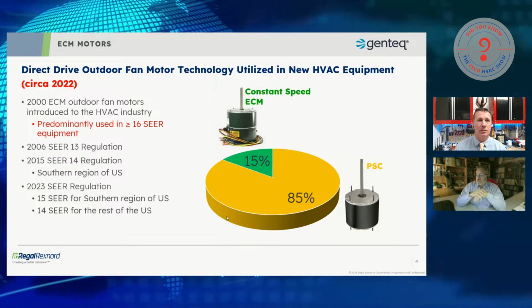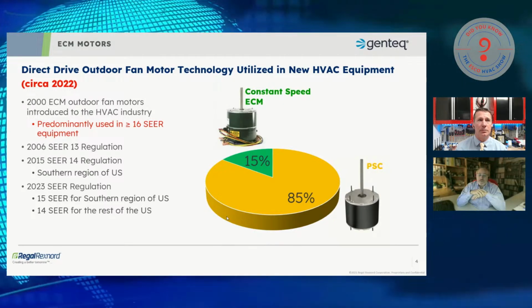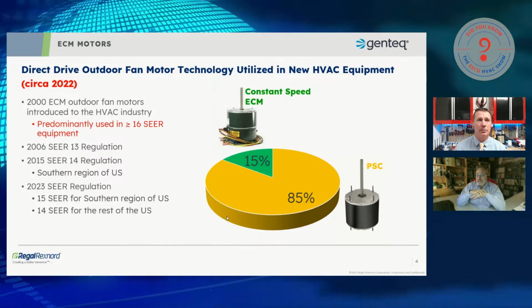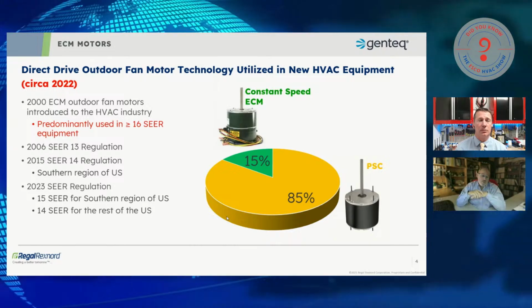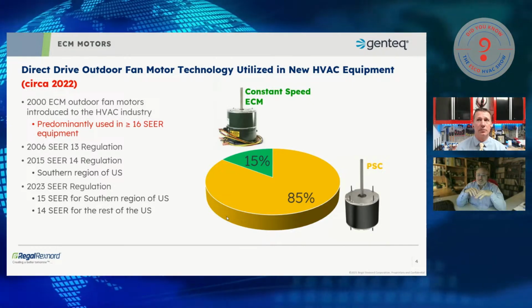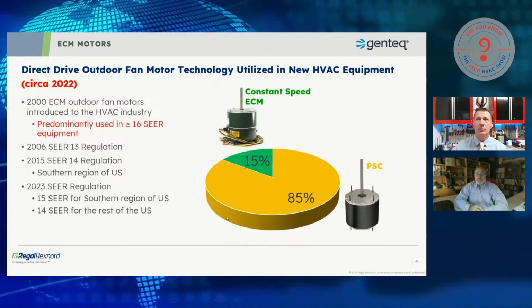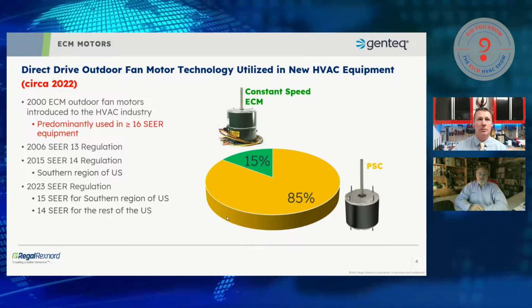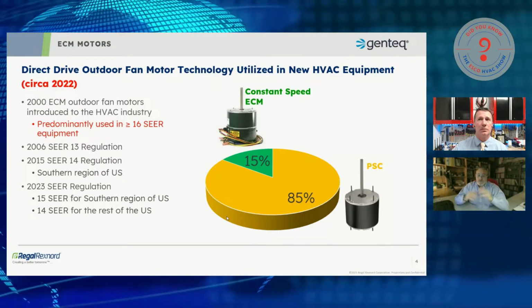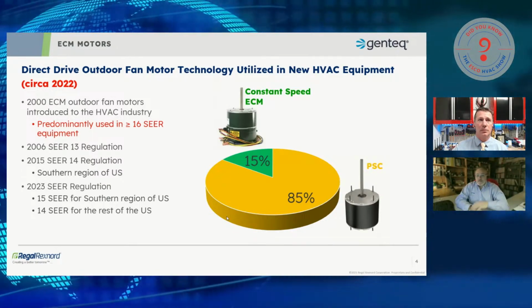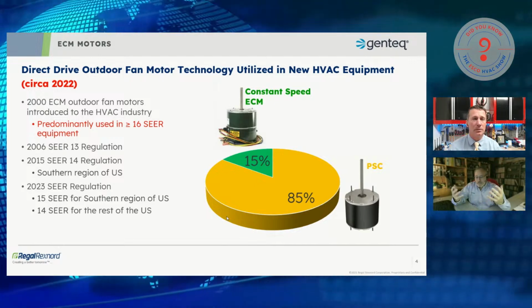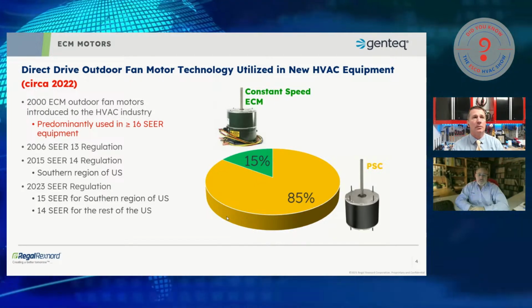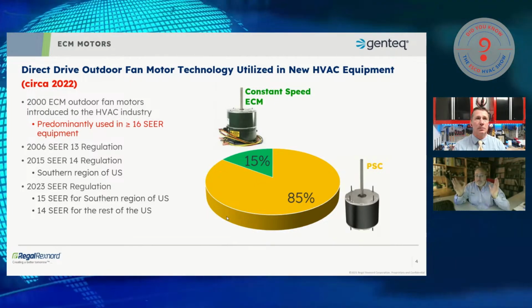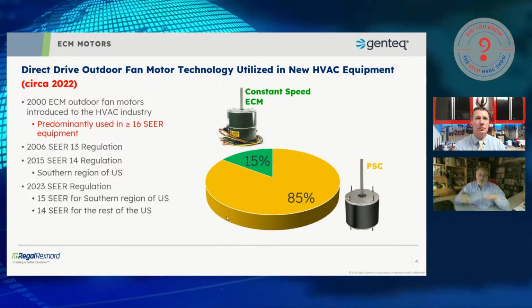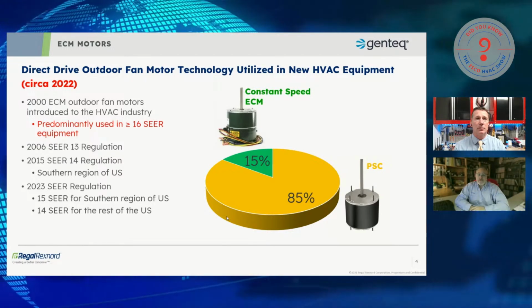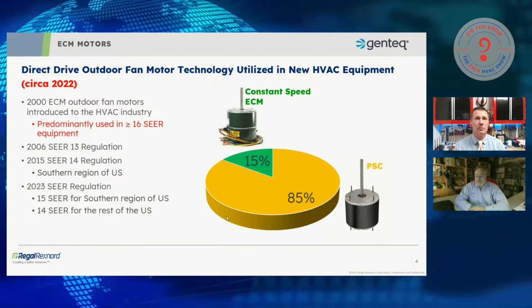So we're still seeing that the ECM outdoor fan motor is used in equipment that's above the minimum SEER rating. Why is that important? Well, it's not necessarily being regulated; it's manufacturers that choose to build higher SEER systems for those regions that can benefit from the higher efficiency. Whereas in my region, 95% two-stage gas furnaces are very common, but not very common in the southern and coastal regions, where they don't have as much need for heating demand.